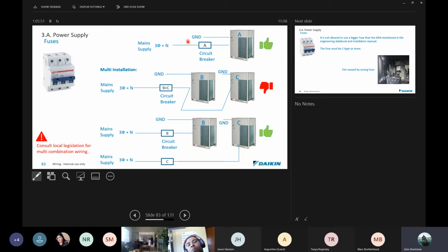What we're looking at over here, each unit must have its own power supply. So what we've got over here is a three-phase and neutral power supply. There must be a separate ground to the unit, and a circuit breaker. You may not daisy chain power supplies between units. This is not acceptable. There were old installation manuals from days of VRV2 gone by where that was acceptable. It's no longer acceptable.